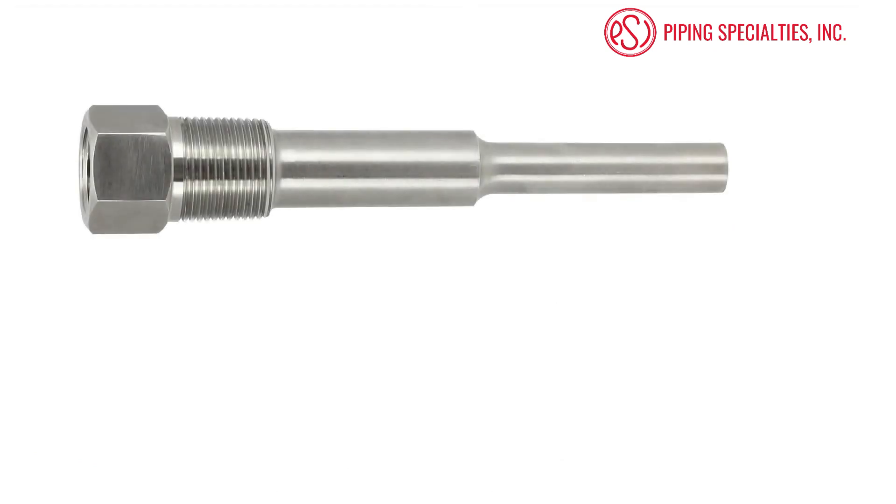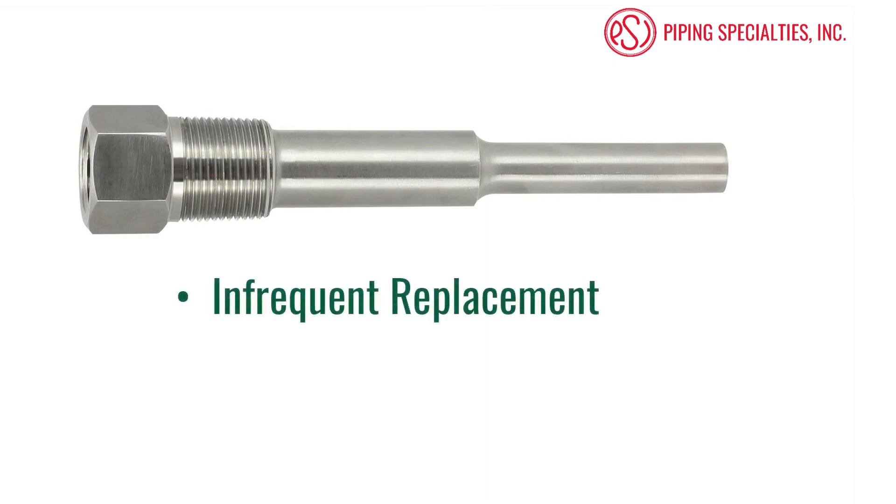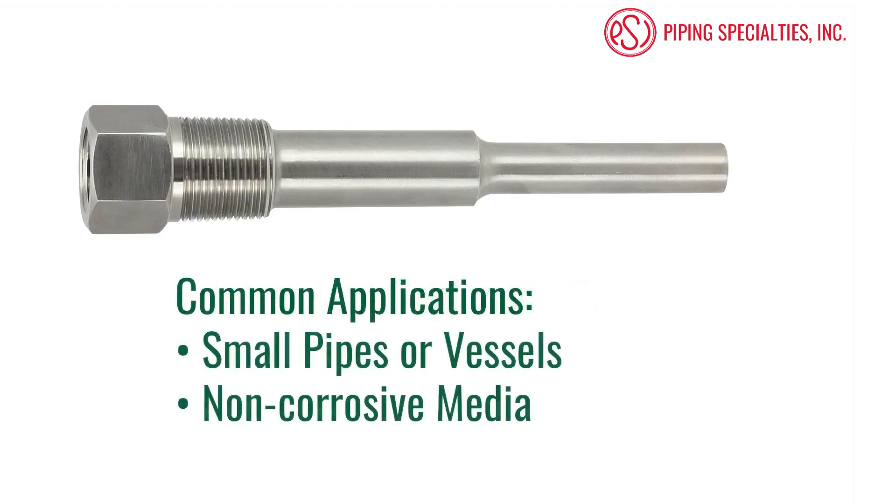The first type of thermowell we are going to cover is a threaded thermowell. Threaded thermowells are commonly used in the industry when the well will not be removed on a regular basis. These wells are normally threaded into a welded fitting, commonly referred to as a weldolet, on the pipe or vessel. Common installations include smaller pipes or vessels where corrosion is not an issue.